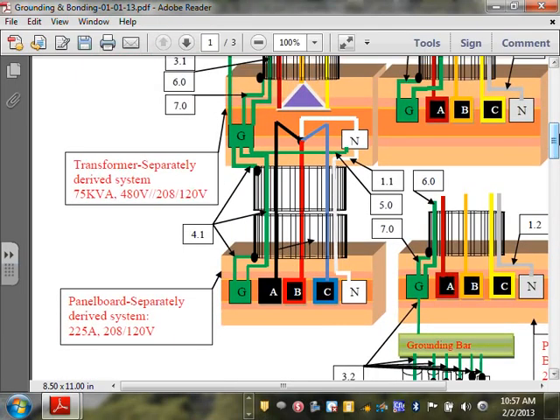Now, I'm an engineer, so remember, this is a 480/277. When you bond for 480/277, it's more strict than bonding and grounding for 208/120, right? If it's 208/120, you could get away with half an inch or three-quarter-inch EMT conduit with just the connector, right? Connectors that will bond the two together. If it's 480/277, you have to have a special bonding connector that has more teeth to eat into the panel.